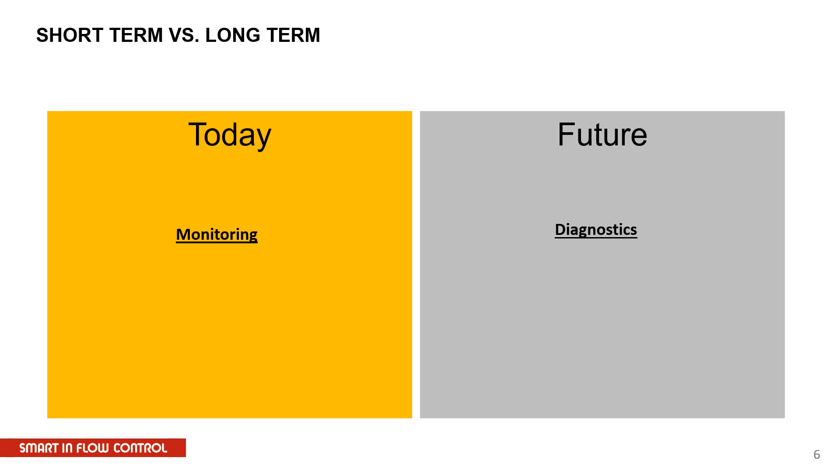Today we're standing in a situation where monitoring is basically available. We are always doing monitoring by the control system — the pre-programmed conditions in the DCS — which will prevent failures from becoming real catastrophes. The limits there would stop us from creating significant damage. To that you need to add things like SamGuard, our AI-based product, where we look at the same things but don't apply pre-programmed conditions. We monitor the plant according to its own behavior, trying to catch a failure as early as possible.